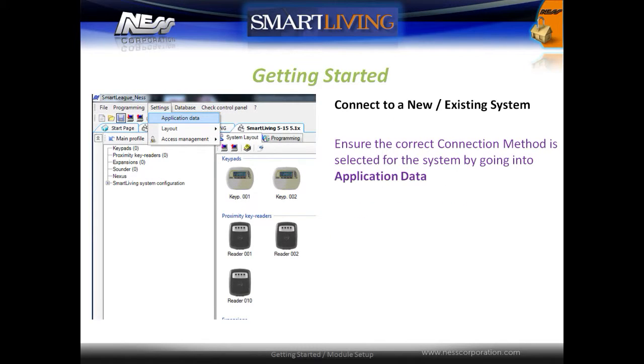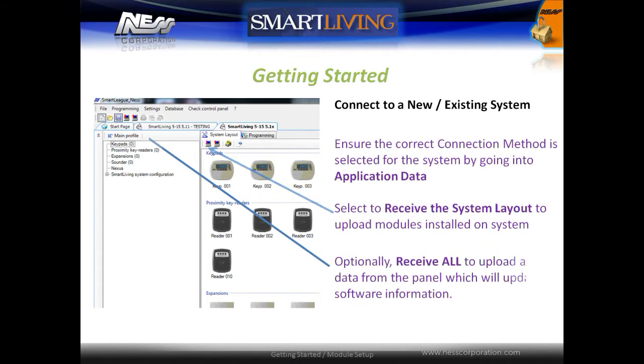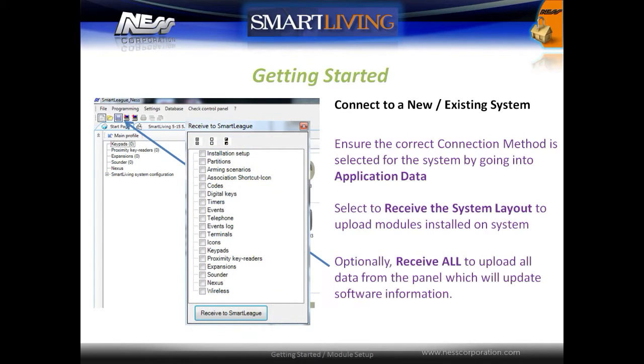Ensure the correct connection method is selected for the system by going into Application Data. Select the System Layout tab, and then click Upload to upload all modules installed on the system. Optionally, select Receive All to upload all data from the panel, which will update the software information.